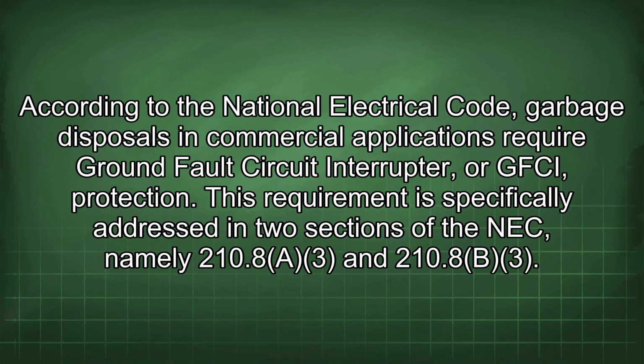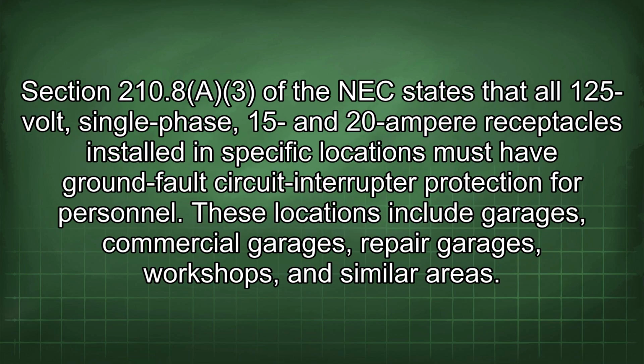According to the National Electrical Code, garbage disposals in commercial applications require ground fault circuit interrupter, or GFCI, protection. This requirement is specifically addressed in two sections of the NEC, namely 210.8(A)(3) and 210.8(B)(3). Section 210.8(A)(3) states that all 125-volt single-phase 15 and 20 ampere receptacles installed in specific locations must have ground fault circuit interrupter protection for personnel.